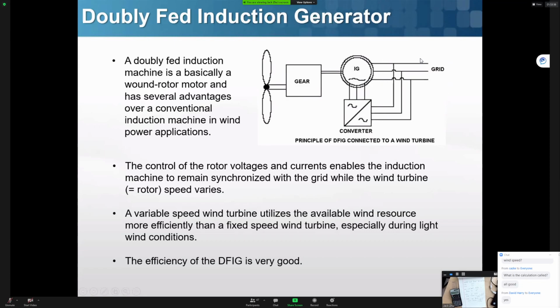But if you do it that way, you have to use a bigger inverter, because it depends: if you have a 100 kVA generator, your inverter has to be rated 100 kVA or larger, you might even have to overrate your inverter a little bit. But this way, even if you have a 100 kVA generator, you can probably just use a 30 or 40 kVA inverter, because you're only feeding a small amount of current into this rotor circuit.